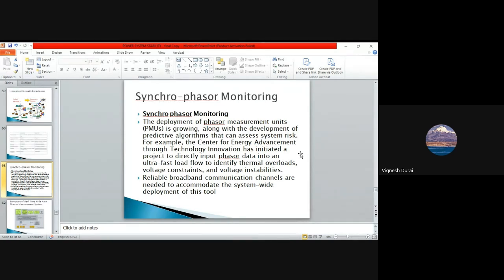These PMUs are implemented by the National Load Dispatch Center. See, as it is very costly, they have not installed them in every area. Selectively, they have installed them. I think around 500 to 600 PMUs are installed all over India. This PMU will scan the entire system. They have installed it in 400 kV networks. So it will scan the system every second, 48 times every second, and it will give the power flow. How much dispatch is happening, everything will be monitored by NLDC through PMU.